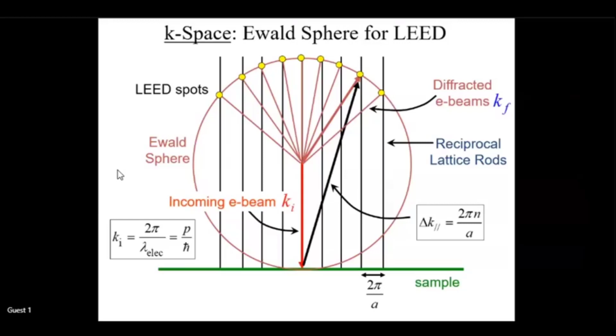Now, if you look at the LEED apparatus, the instrument, how it looks. Basically what you require is a good electron gun, which is shown here as this black hollow cylinder in the planar direction. And the plane of the sample is perpendicular to the beam of electrons. Once the diffraction takes place, when 2d sin theta equal to n lambda is satisfied, you have the scattered electrons going in all different directions. And just like in a grating, where we have first order diffraction, second order diffraction, exactly in the same way you get diffraction because of the strong scattering cross section.